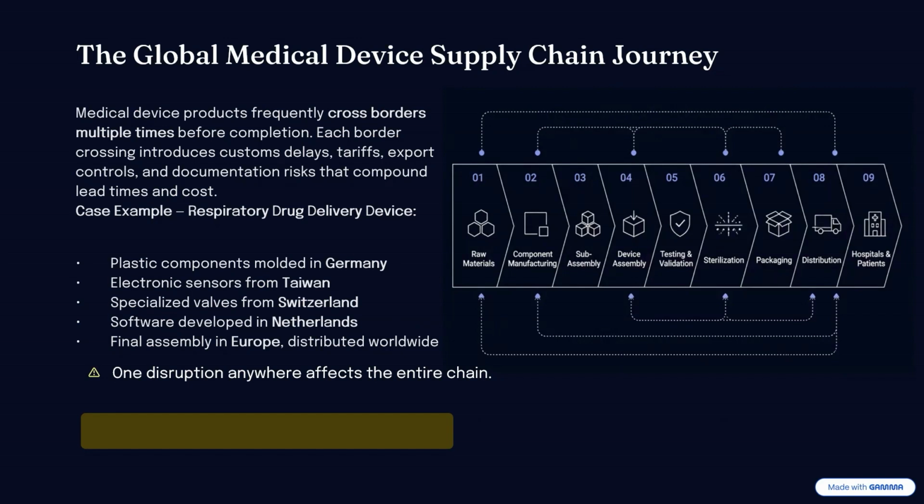Even if we think about the plastic components, it looks very simple, but the process itself to mold a medical device, I can quote one practical example, where the operator somewhere sitting in one country, I won't name it here, is not capable enough to maintain the manufacturing conditions for a specific plastic molded part. If you don't do it, it will have a discoloration.